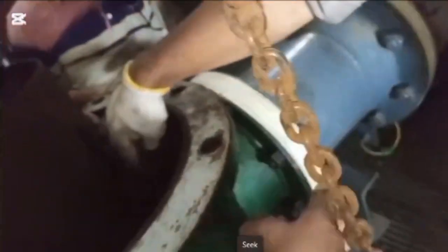This is the ejector unit, and one of the ejectors had its base damaged due to corrosion, so we changed the ejector to a new one. But the new ejector's connecting pipe was somewhat different from the used one, so we had to do some work to connect this new ejector.